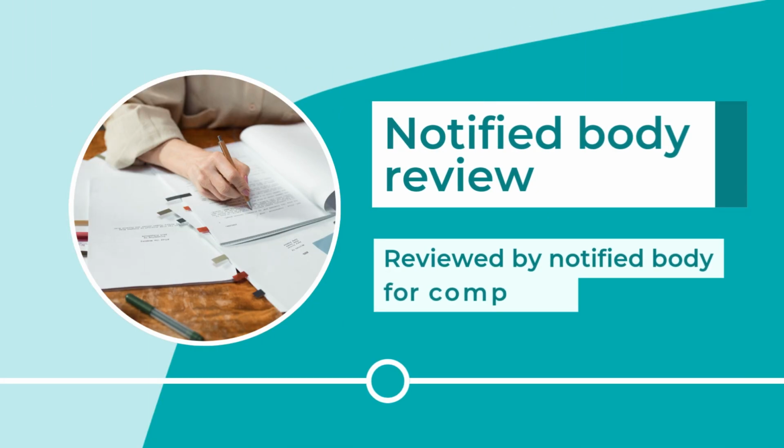When the technical file is complete, a notified body audits the quality management system and, where required, reviews the full design dossier or the representative type sample. Only after all observations are resolved will a CE certificate be issued.